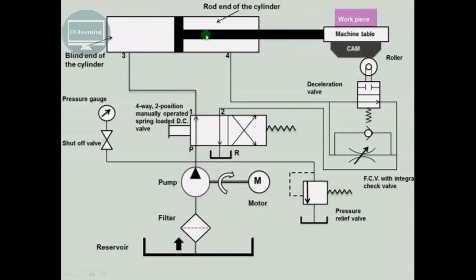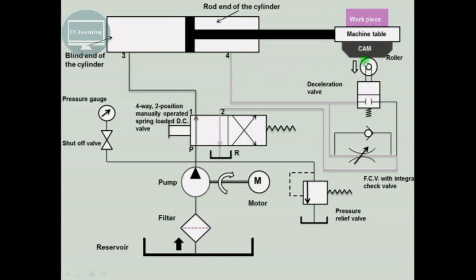The fluid forces the piston and piston rod to move in the forward direction, along with the machine table, cam, and workpiece. The cam touches the roller and presses it downward. Initially the valve is normally open; once the roller is pressed down the valve moves to the blocked position. Since the cam has touched the roller, we now want to reduce the speed of the machine table so that work can be performed on the workpiece at a reduced speed.